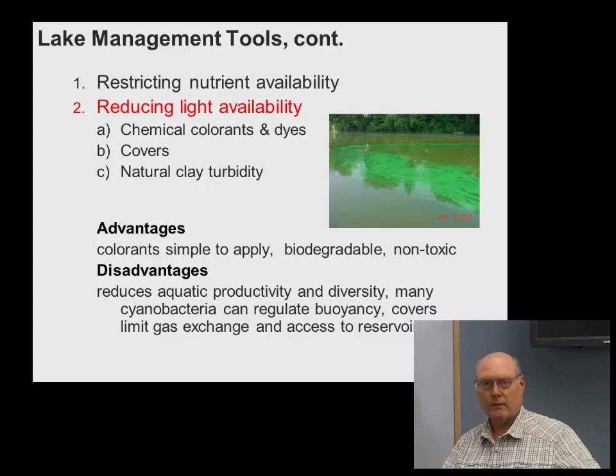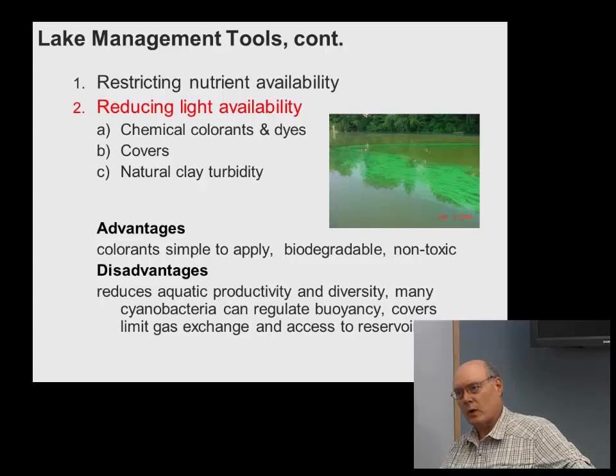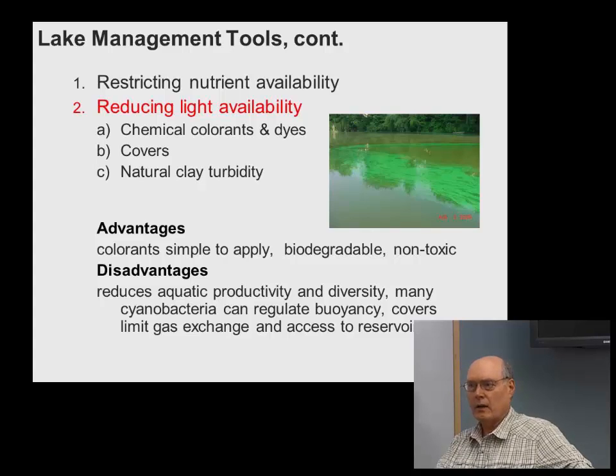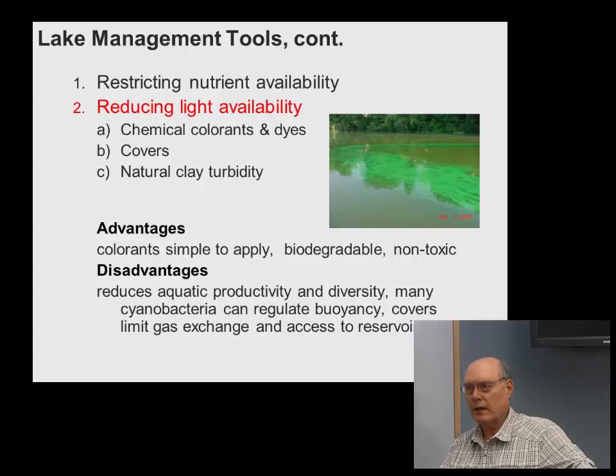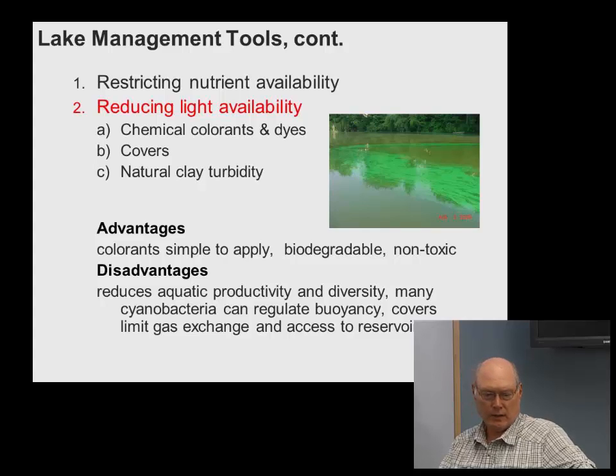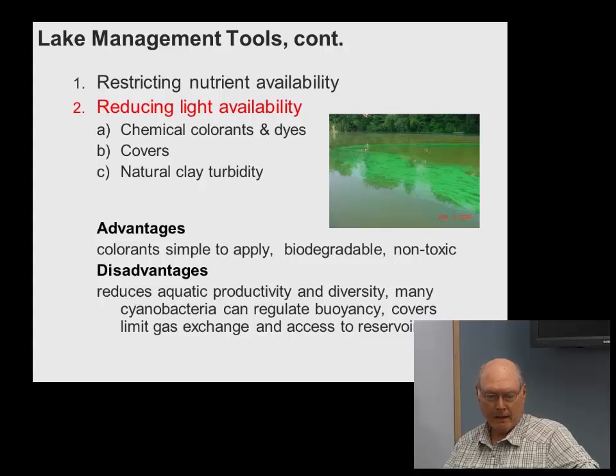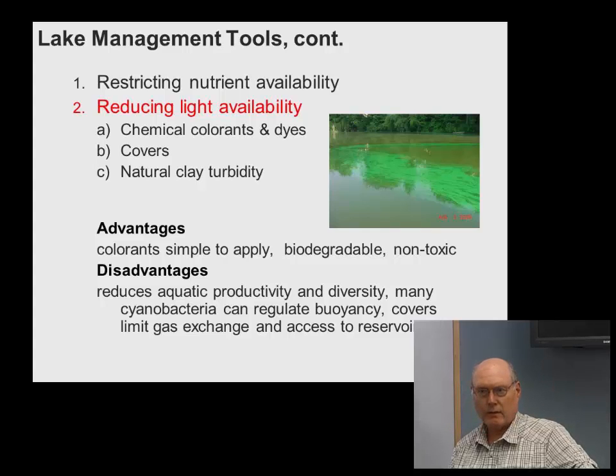Covering reservoirs is increasingly used — I've seen many communities now literally covering their holding reservoirs to reduce light and bloom formation. With covering, you'll need additional aerators to prevent the system going anaerobic and causing taste and odor issues. Natural clays can also be used to create turbidity and reduce light penetration.